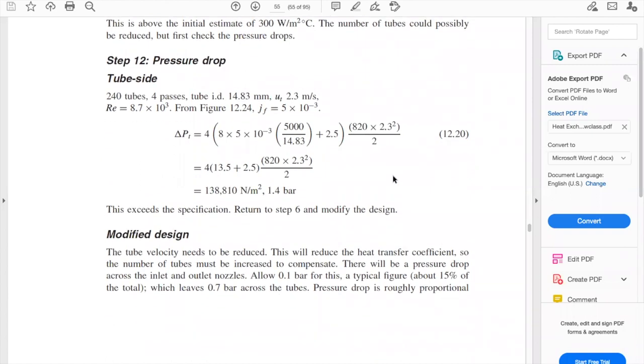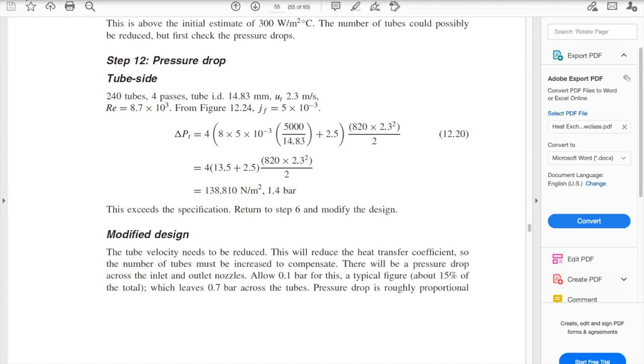We already established that we are going to use 240 tubes, 4 passes, and this is the inner diameter of the tubes we are employing. The velocity already doubled is 2.3 meters per second. We need to recalculate and get the Reynolds number, but in order to get the delta P, we are going to use equation 12.20. The delta P inside the tube requires a correction factor, JF, which we can get from figure 12.24.